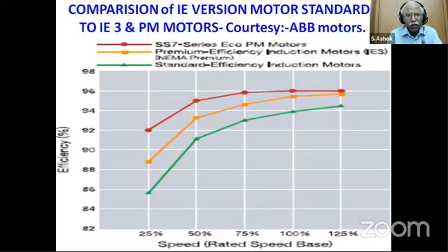The IE2 motor has become mandated under the ministry and the gazette. AC OEMs are supposed to use minimum IE2 motors only, as per the gazette from January 2018. Now, when you are making the IE2 motor VFD compatible, then you need to go for an IE3 motor only, so that the motor becomes VFD compatible, and it is very much useful for air conditioning applications.